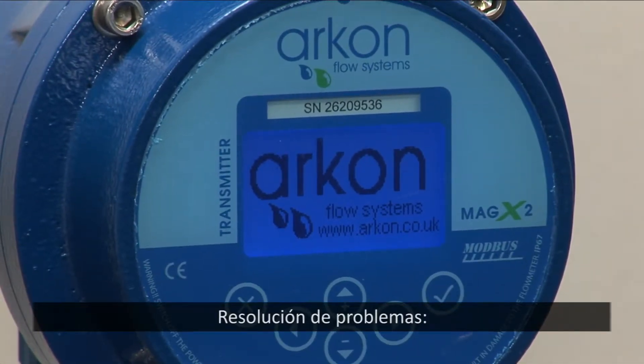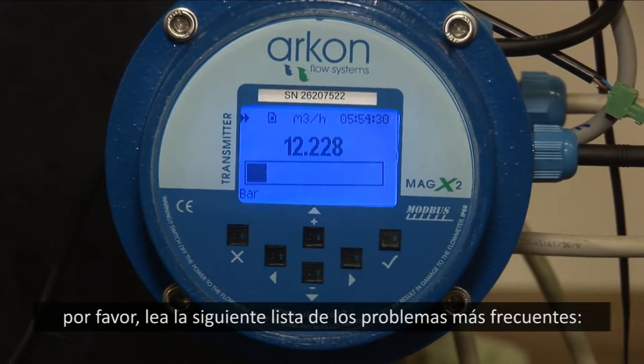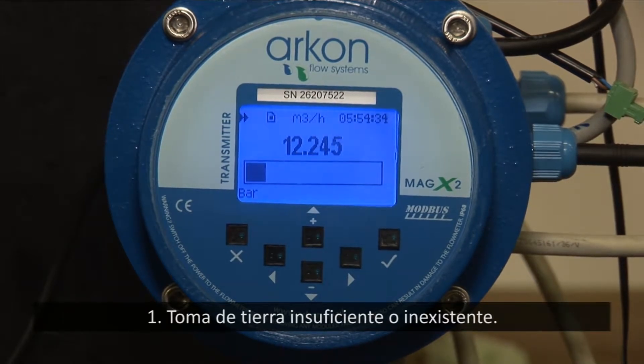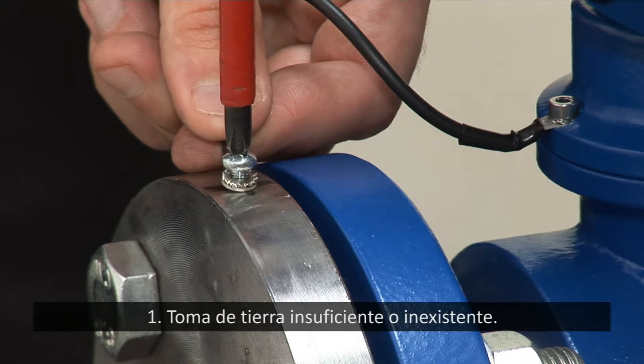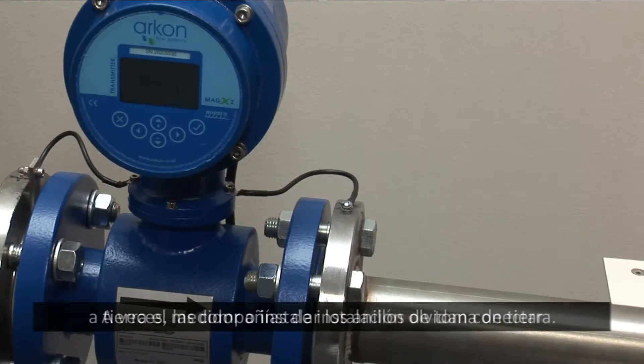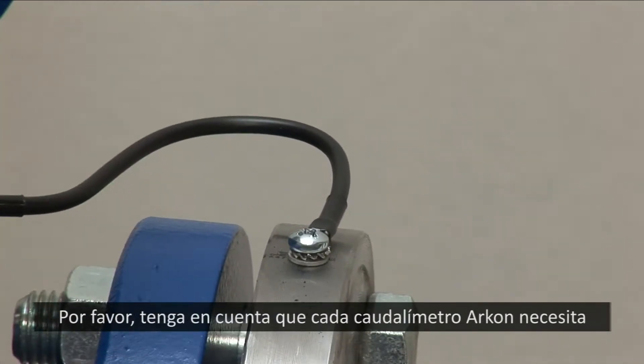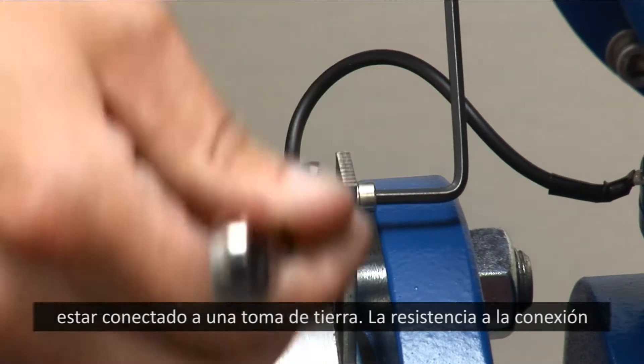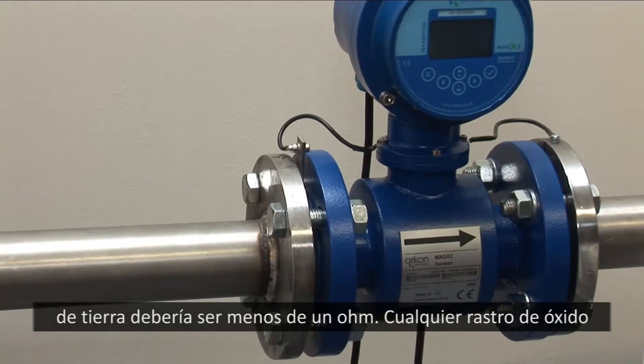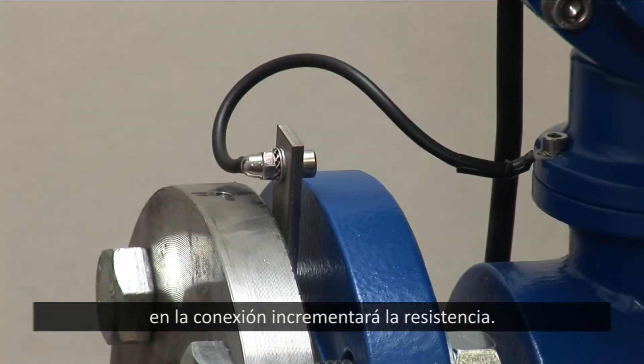Troubleshooting. In case your readings are unstable, here follows a list of the most frequent problems. 1. Insufficient or missing grounding. Sometimes installation companies forget to ground the meter or do not install earthing rings. Please note, each Arkon flow meter needs to be grounded. Resistance to ground should be less than 1 ohm. Any rust or poor connection will increase its resistance.